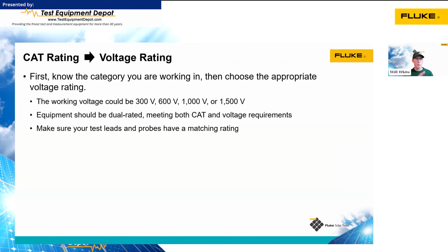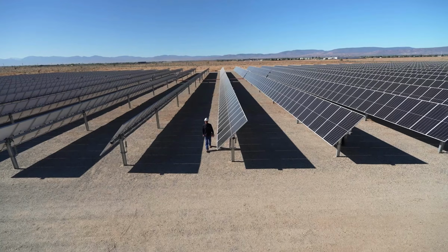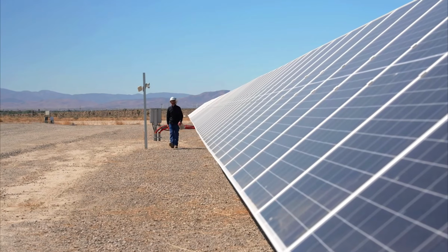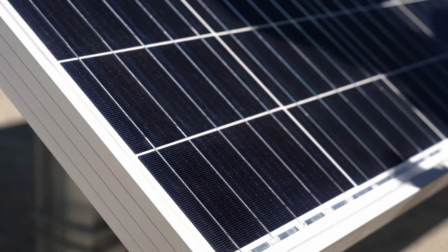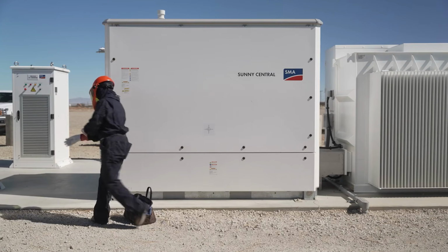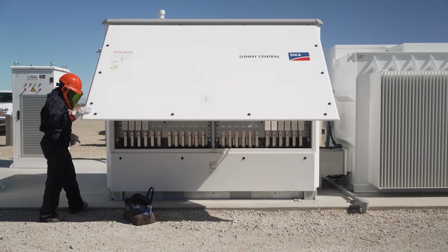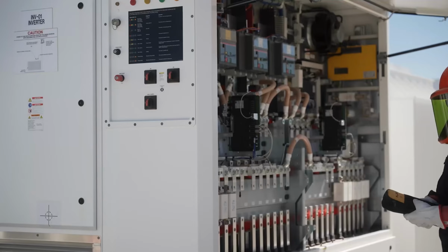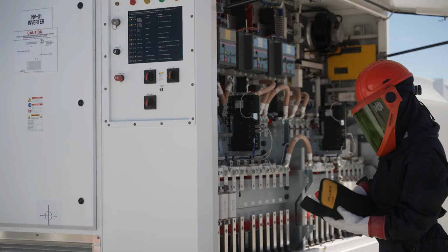Once we know what environment we're working in, we need to know what voltage we're going to be working on. In solar, we measure everything from 30-40 volts of a single solar module up to 1500 volt DC systems. AC side could be anywhere from 120, 240, 208, 480, even up to 600 or 800 volts on the output of utility scale inverters. When we look at our tools, we want to make sure that we have the appropriate category rating. So category 3 for solar arrays, category 4 if we're working at the point of interconnection, and we need a voltage rating higher than the voltage that we are testing. And so we need both those category and voltage ratings.